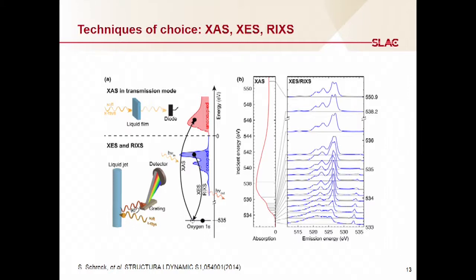And by changing the incoming energy, we can see what gets transmitted through the sample, and this gives us the X-ray absorption spectrum. At the same time, if there is a means to track the energy of the photons that come out, from the electrons that fill that empty state, we can get X-ray emission spectroscopy. And this really tells us a lot about the occupied density of states. And in order to do this, we need to have a grating spectrometer. For the soft X-ray regime, this is by far the method of choice, to disperse the beam and send it to a detector and measure each color individually.